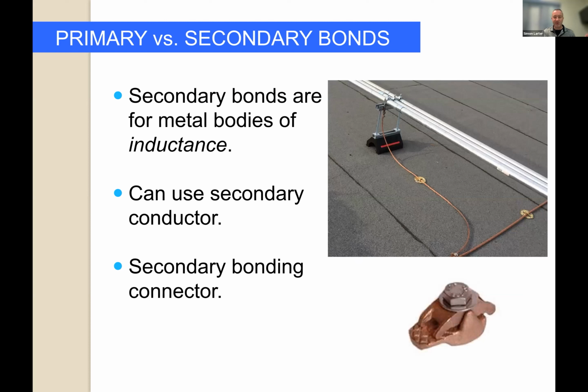Secondary bonds are for metal bodies of inductance. They are not subject to a direct strike. The cabling is not supposed to carry any current. So we use the secondary conductor. It's thinner. It's maybe hard to tell on that photograph, but the horizontal conductor running from the middle of the bottom up to the right, that is a main sized copper conductor. The copper that goes back and connects up to that pipe support, that's a secondary conductor.